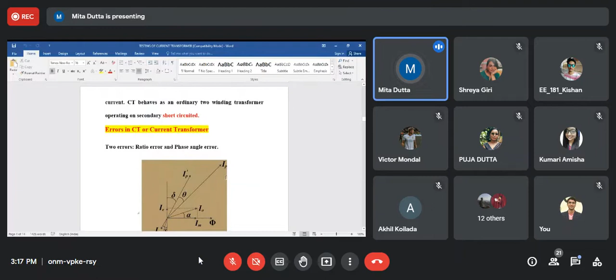So now, to find out the ratio and phase angle of a CT, we have to consider the phasor diagram of the CT. This will be the phasor diagram of a CT, which is more or less equivalent to that of a power transformer. In power transformers, we take phi as the reference phasor because the flux phi is common to both the primary and secondary windings.